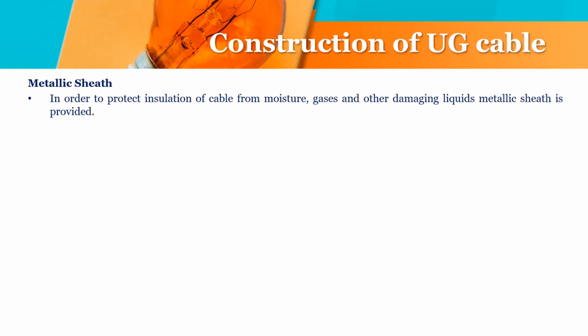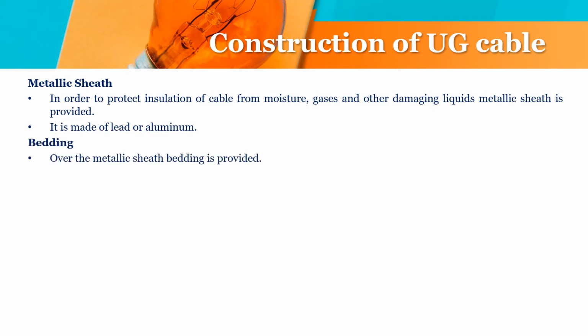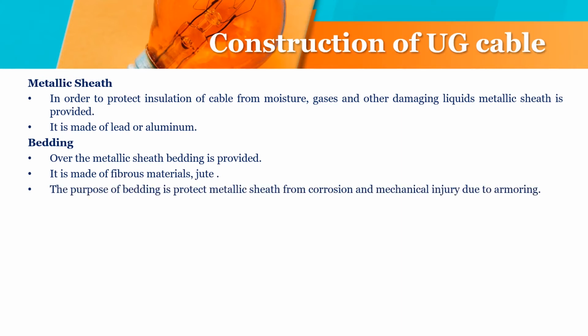Construction of UG cable. Metallic sheath: in order to protect the insulation of the cable from moisture, gases and other damaging liquids, a metallic sheath is provided. It is made of lead or aluminum. Bedding: over the metallic sheath, bedding is provided. It is made of fibrous material like jute. The purpose of bedding is to protect the metallic sheath from corrosion and mechanical injury due to armoring.